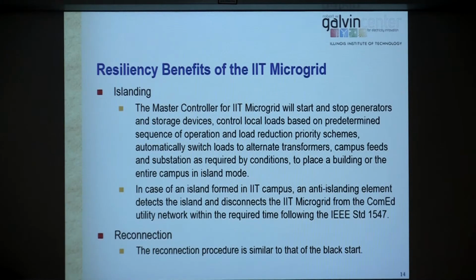So if there is no major outage, which we haven't had in Chicago luckily, we go through this drill about 5 or 6 times a year. What it means is we assume there is a major outage and then we create an island. That could be on a very hot summer day or a very cold winter night. We actually disconnect the campus and see what will happen, and whether we're able to manage voltages, frequency, keep the lights on, keep the dormitories on, and everything else.